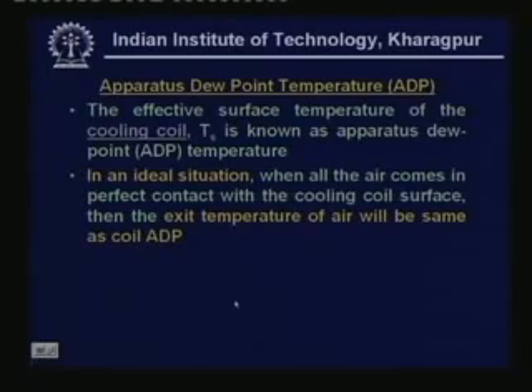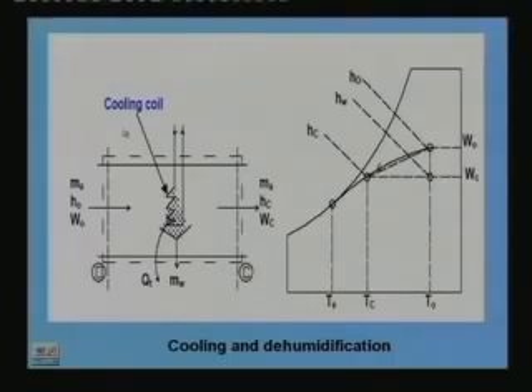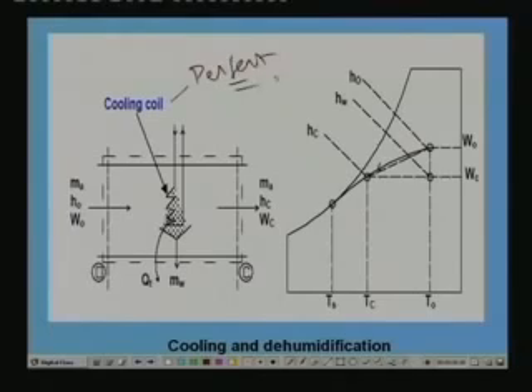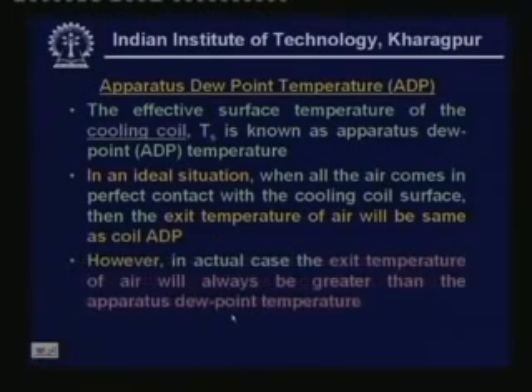In an ideal situation, when all the air comes in perfect contact with the cooling coil surface, then the exit temperature of air will be the same as the coil ADP. That means you have, let us say, a perfect coil, perfect in terms of heat and mass transfer. When this coil is perfect, the heat and mass transfer rate between air and the coil will be maximum, and the exit condition will be at this point. The exit condition coincides with the coil ADP. However, in the actual case, the exit temperature of air will always be greater than the apparatus dew point temperature because of various resistances.